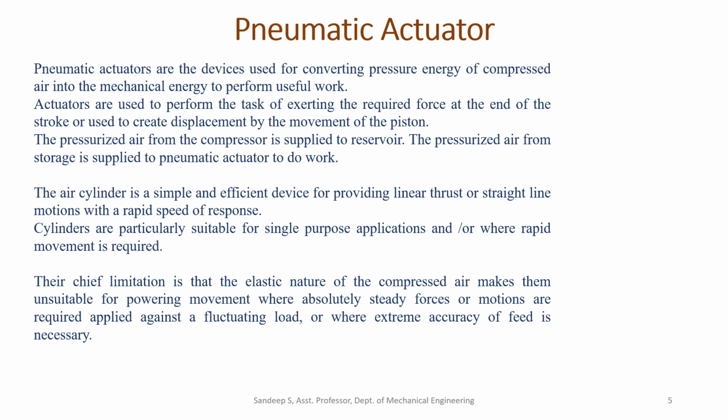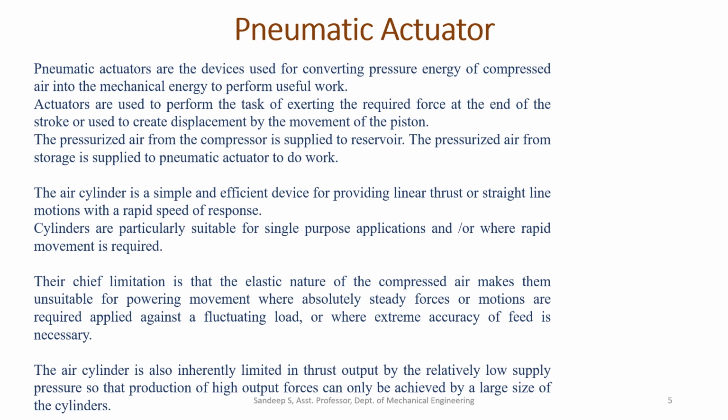The chief limitation is that the elastic nature of the compressed air makes them unsuitable for powering movement where absolutely steady forces or motions are required, where applied against a fluctuating load, or where extreme accuracy of feed is necessary. The air cylinder is also inherently limited in thrust output by a relatively low supply pressure, so that the production of high output forces can only be achieved by a large size of cylinder.